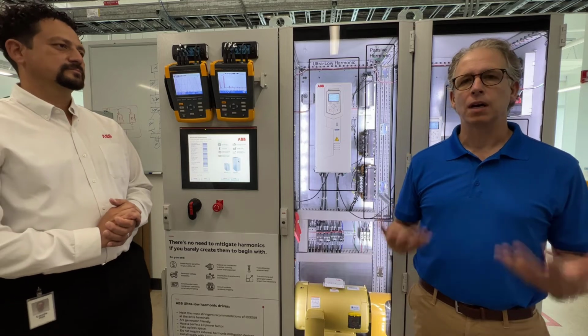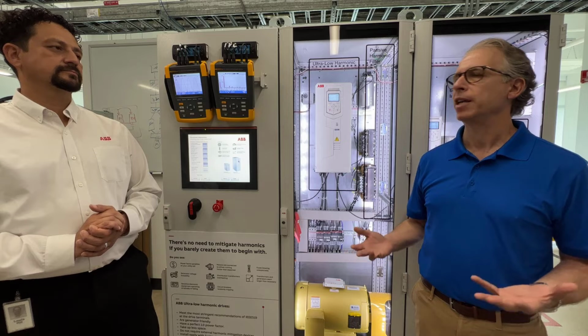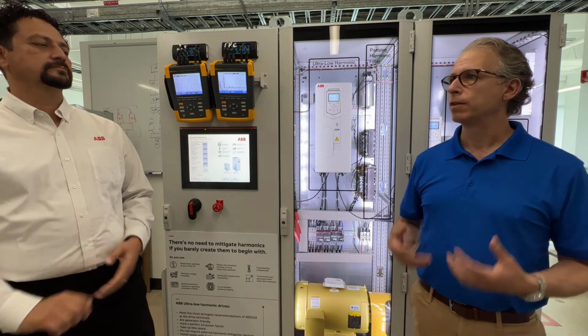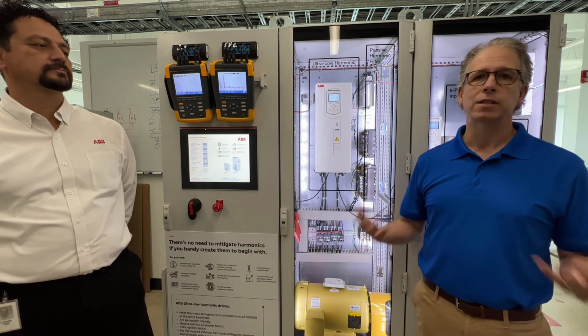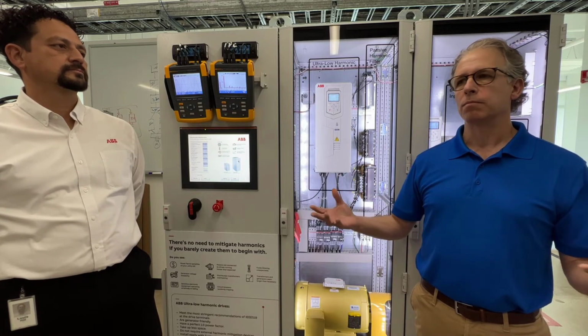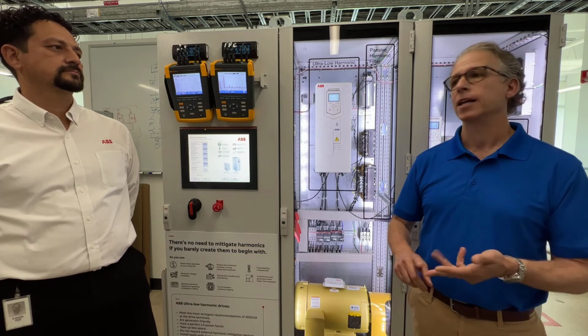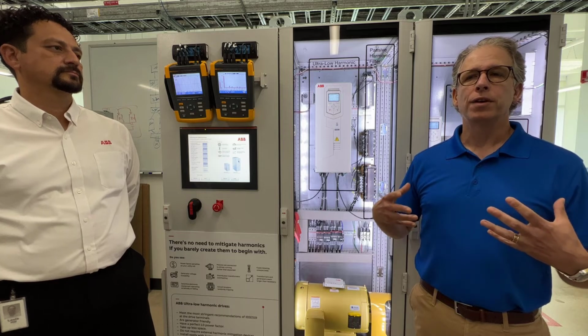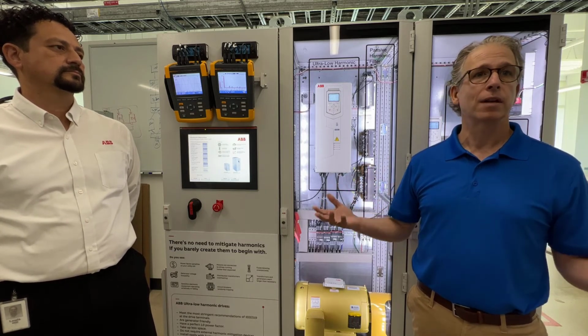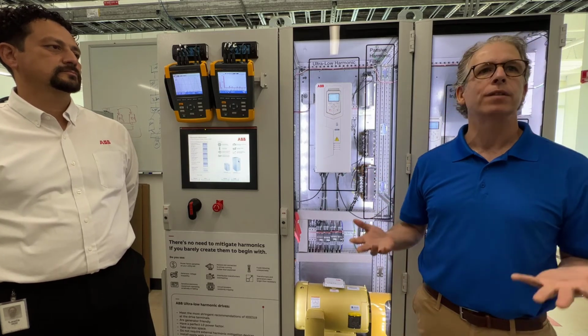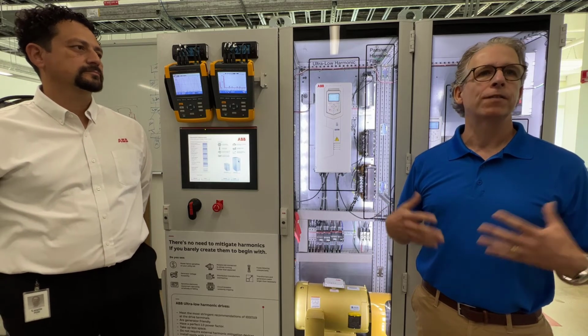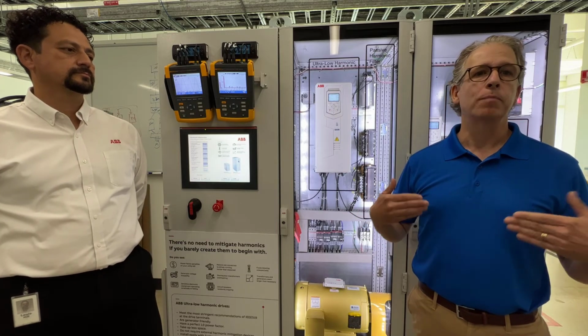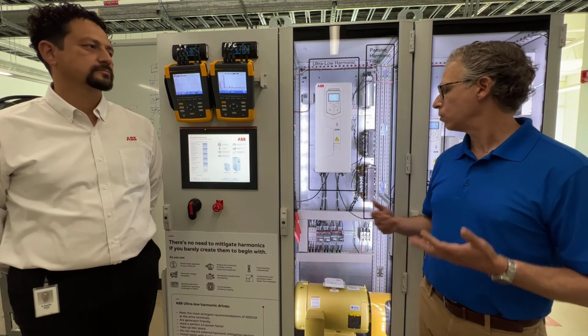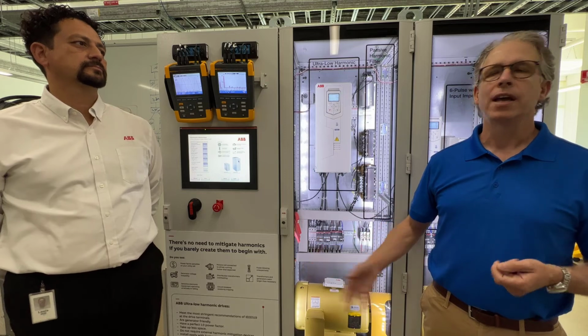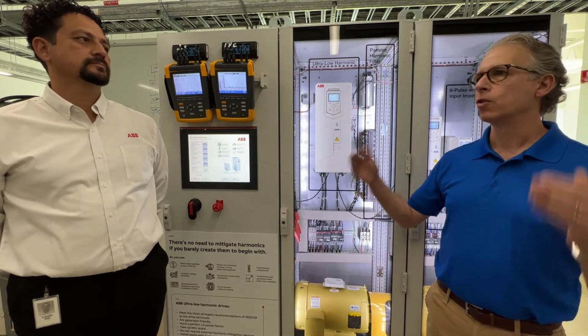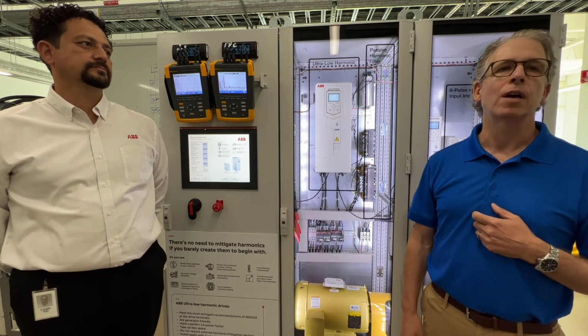At Norman S. Wright, as a mechanical representative, we represent many product lines from many trusted manufacturers, and the design team trusts us to provide the most energy efficient solutions for their projects, especially in California. As we select equipment on projects, whether chillers, air handlers, exhaust fans, or air handling units, the number of VFDs on the project starts to expand, and now we have more and more nonlinear loads on the building grid. One of the things we offer as a solution is a harmonic analysis, and we present a study to the design team to determine if we meet IEEE 519 or not. When we don't, we suggest using the ULH technology to reduce that harmonic distortion and meet IEEE 519 requirements.